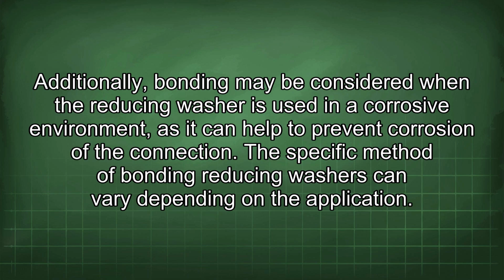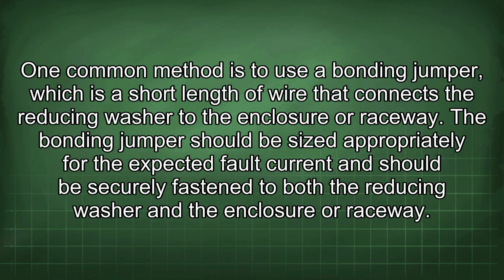The specific method of bonding reducing washers can vary depending on the application. One common method is to use a bonding jumper, which is a short length of wire that connects the reducing washer to the enclosure or raceway. The bonding jumper should be sized appropriately for the expected fault current and should be securely fastened to both the reducing washer and the enclosure or raceway.